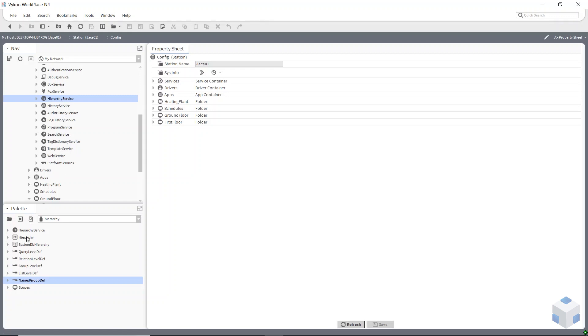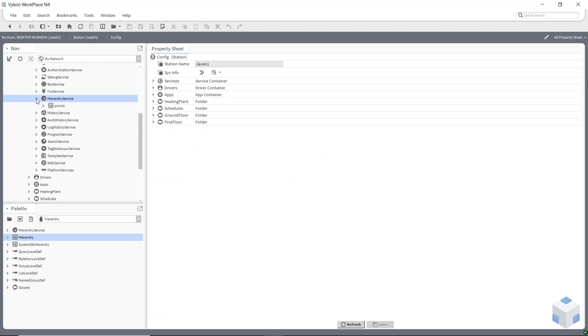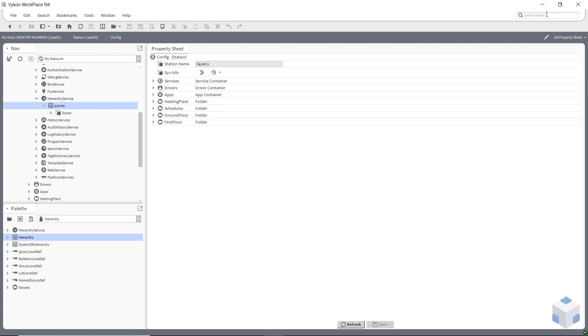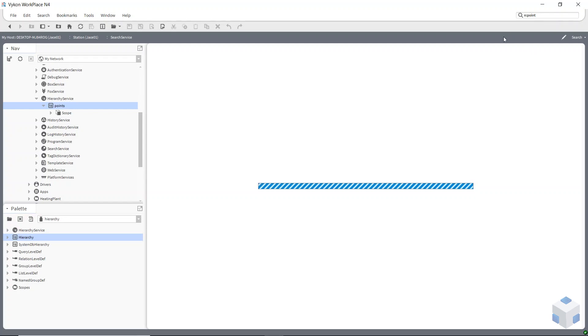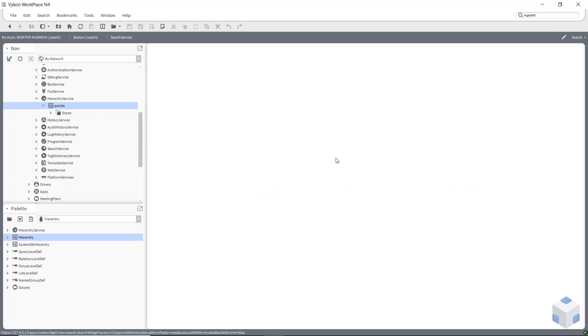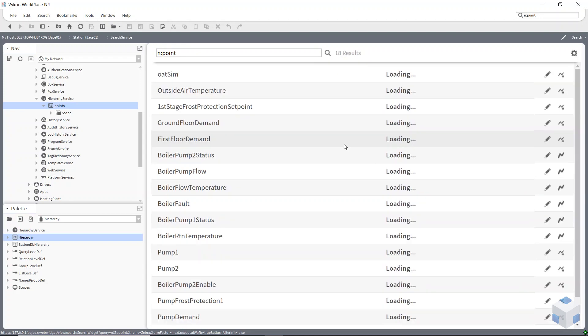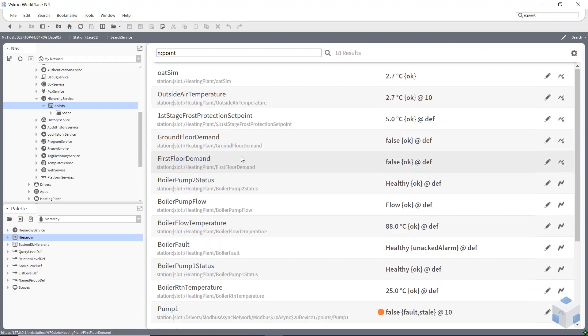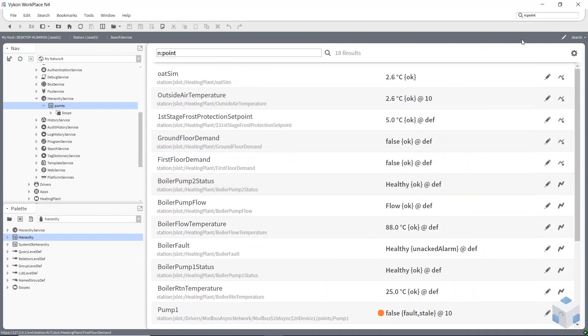To start a hierarchy you have to drop a hierarchy component onto your hierarchy service. I'm going to do a very simple hierarchy initially — it's going to be my points. If I go to quick search and do n colon point — n being the Niagara namespace — every point on my station has got an n point tag on it by default. It's an implied tag added using a Niagara tag dictionary. I'm going to do the same thing but put it into a query.